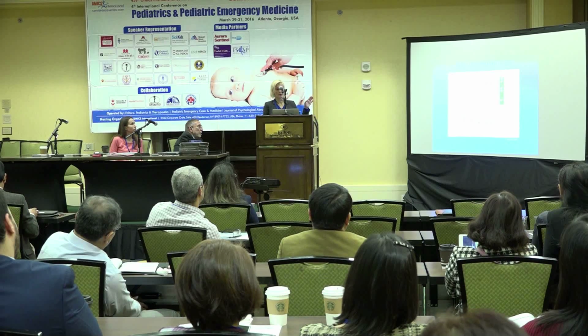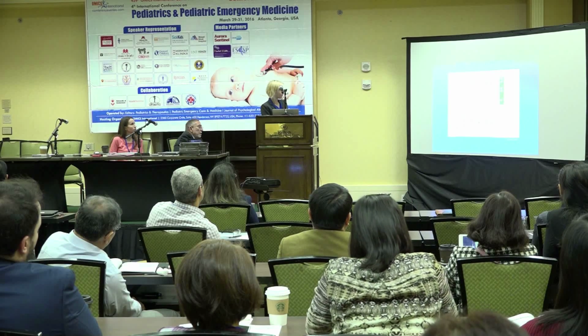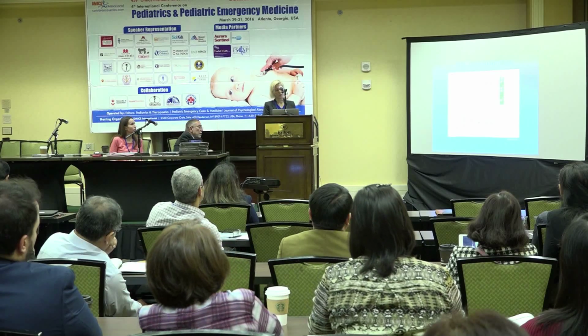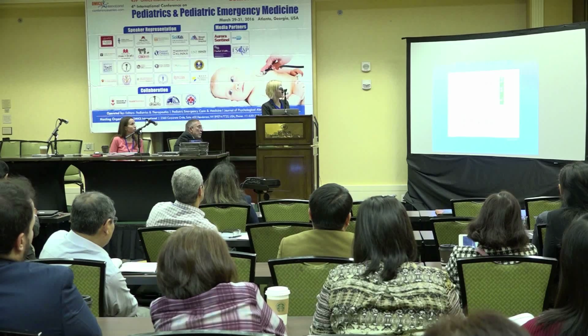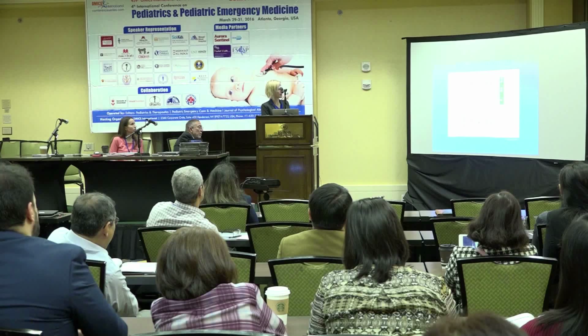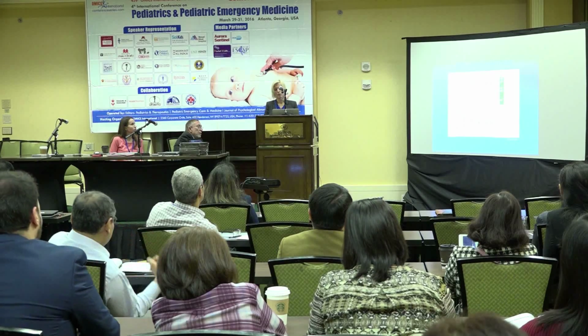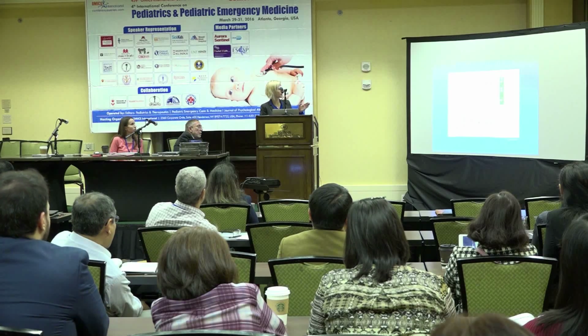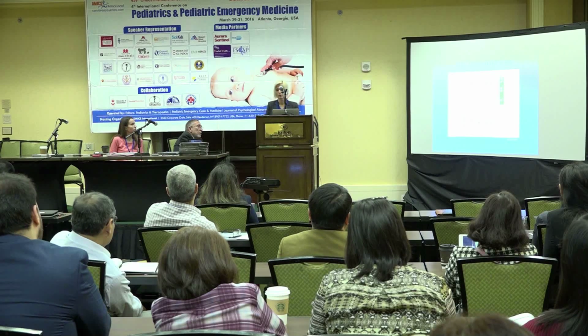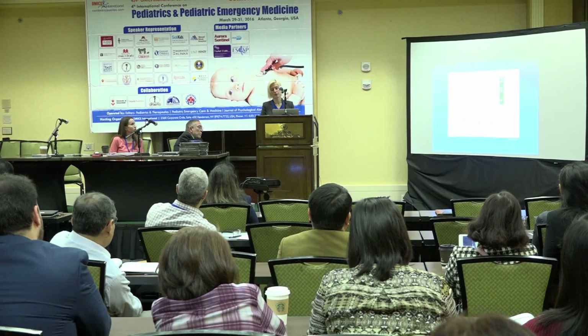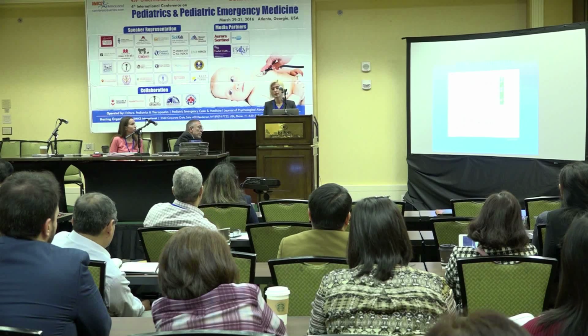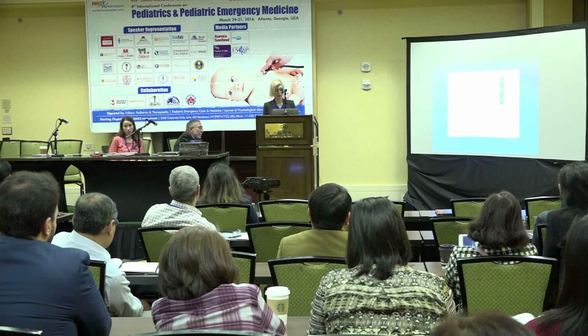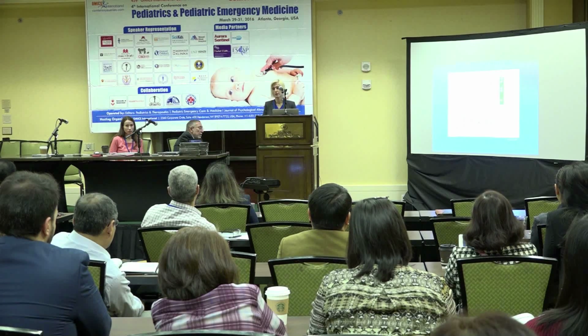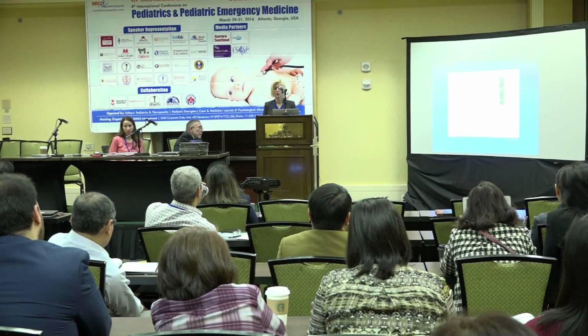Very briefly, this is the principle, just the Beer-Lambert law, and the idea is, the more wavelengths your device emits, the better you can discriminate between reduced hemoglobin, oxygenated hemoglobin, and anything else, melanin, for example, if you have dark-skinned patients. And so what we did is to get to this new Elite ForeSight device that we tested, which at that point was not validated or approved by the FDA. So the company approached us and said, would you be interested in validating this for neonates and peds? And we said, yeah, we can look into that. The idea is you have a better discrimination, specifically for dark-skinned patients and in particular for patients who are cyanotic. And this one was obviously for our pediatric cardiac patients. Many of them have original SATs in the 80s, which is considered normal, obviously very interesting.